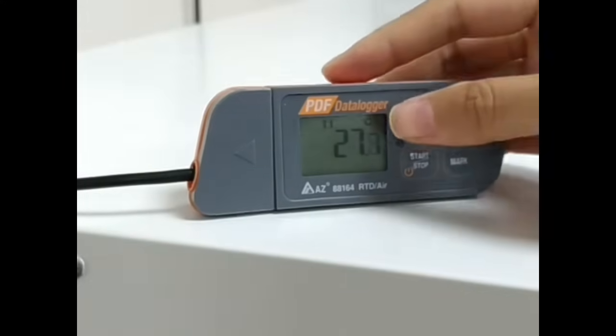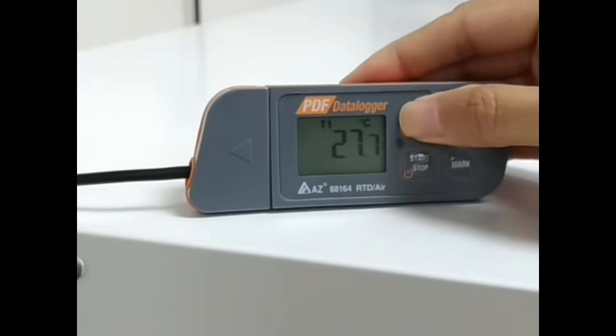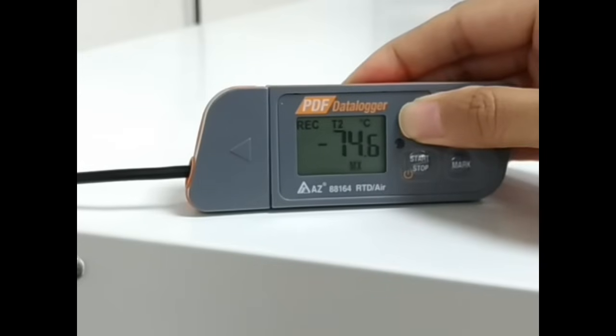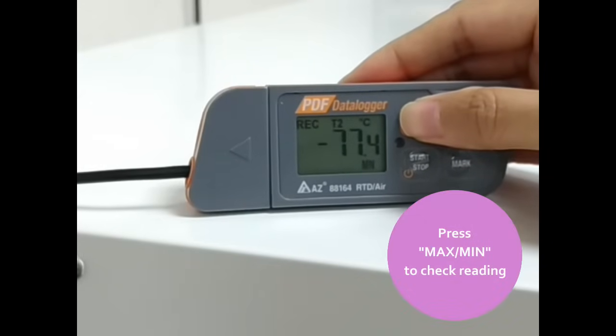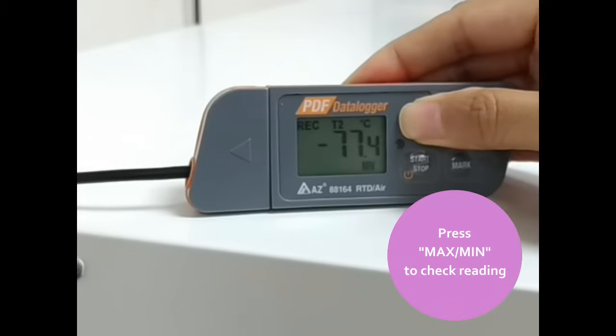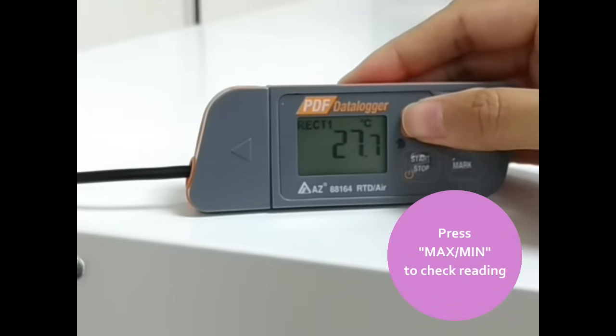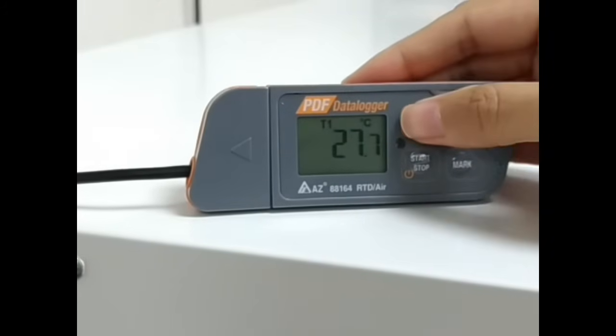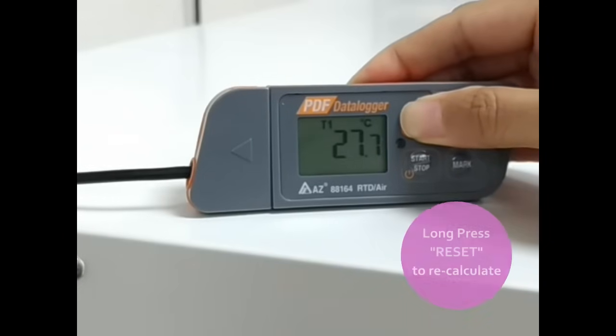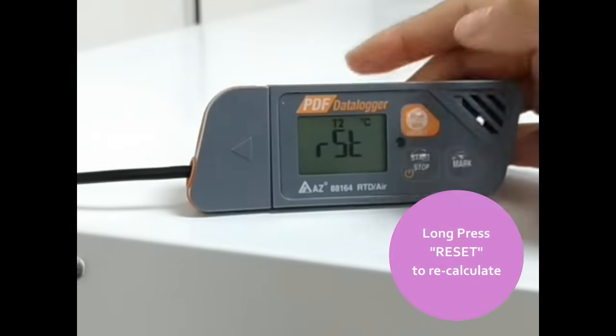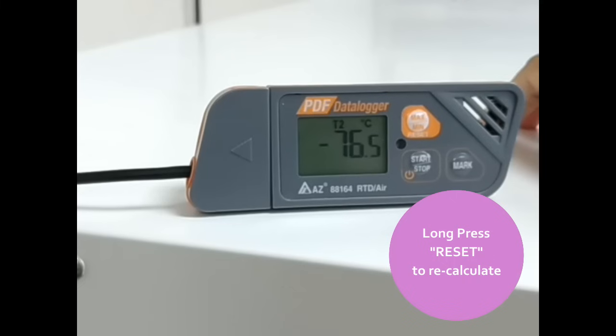You may download the recorded data once a week, so how do you know the maximum and minimum temperature of each day? It is really easy. Just press the MAX/MIN key, and you can read the maximum and minimum temperature counted from the previous reset. After checking, you can long press the MAX/MIN key for 3 seconds to reset.